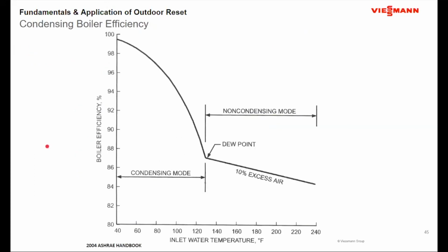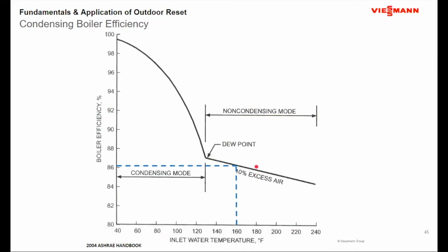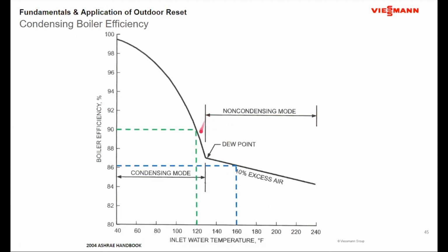Okay. Now, particularly if I'm doing a condensing boiler, outdoor reset's really where the saving is built. So this happens to be a curve showing the efficiency of a condensing boiler versus inlet water temperature. Standard curve out of the ASHRAE manual. So if I run at a design outdoor water temperature of 180 degrees with a 20-degree drop, and I'm doing a condensing boiler, from the generic numbers, that works out to a little bit more than 86% efficient. But if I can drop that water temperature through outdoor reset control, let's say I drop it down to 120, all of a sudden that 86.5% efficiency goes up to 90%.